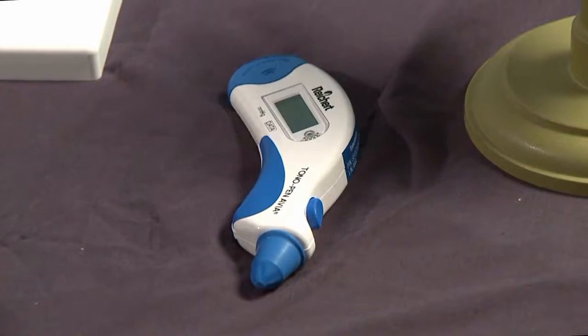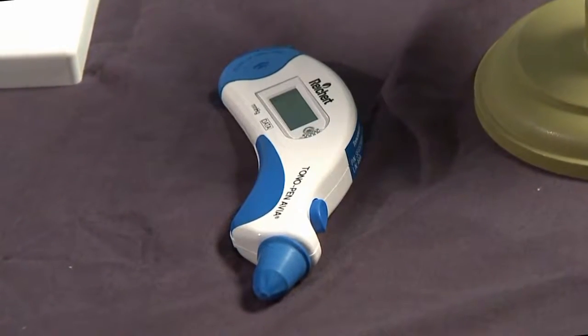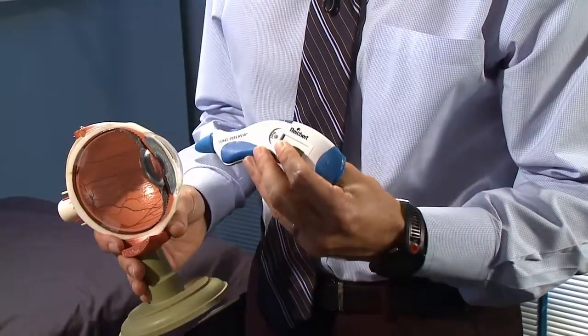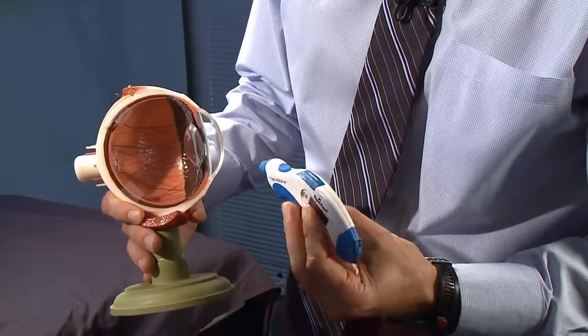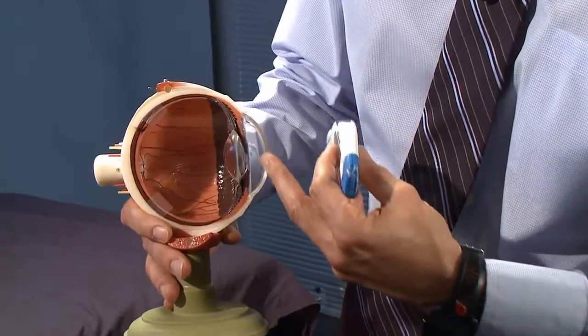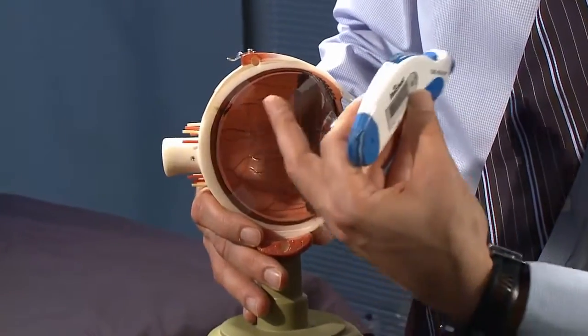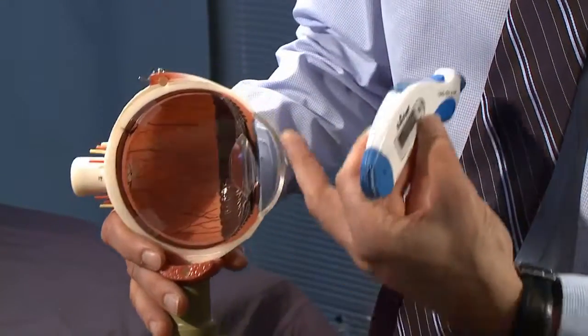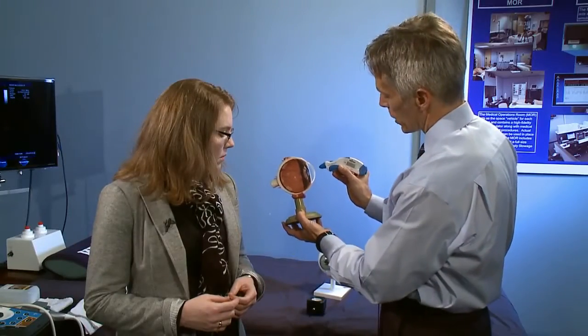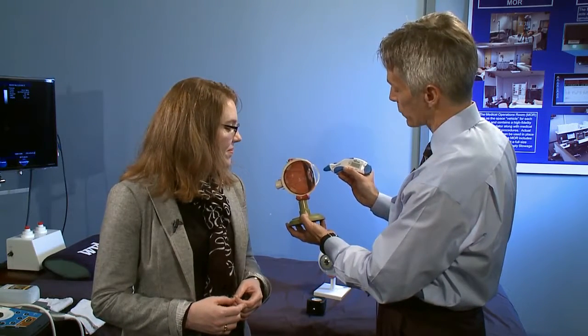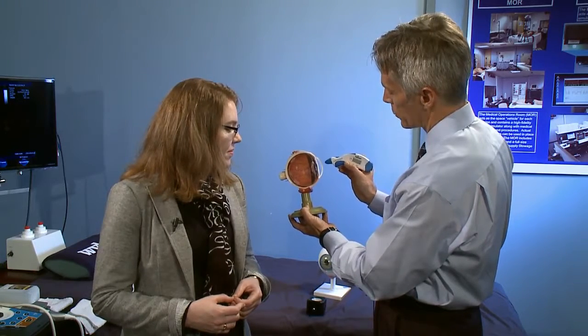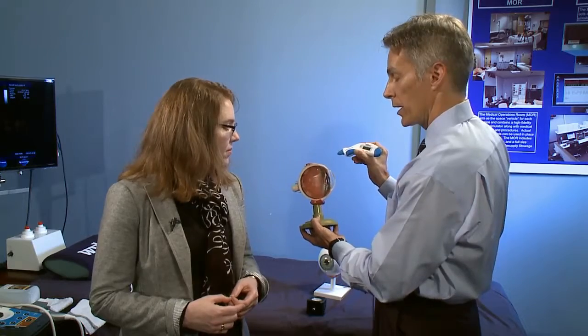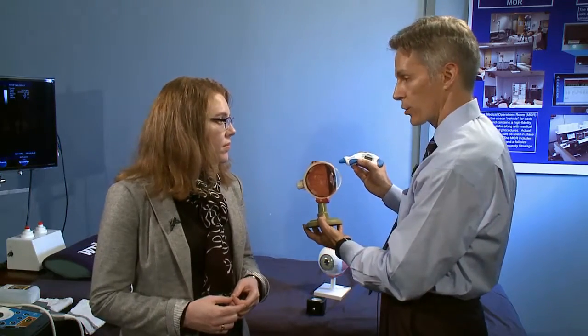Okay, and I think today we're here in particular to learn more about the tonometer. That's right. So what I have here is the tonometer, the tono pen, which we use to measure intraocular pressure in flight. And here's a model of the eye, it's a cutaway of the eye. What you have here is the anterior chamber, this is the cornea, and then we have the posterior chamber, and then you see the white part of the eye or the sclera. The astronauts will anesthetize the eye first with an anesthetic, it lasts for just a few minutes, and then they tap on the eye. An operator will tap on the eye and get a measurement, and that way we can follow the pressure in the eye over the course of the mission.